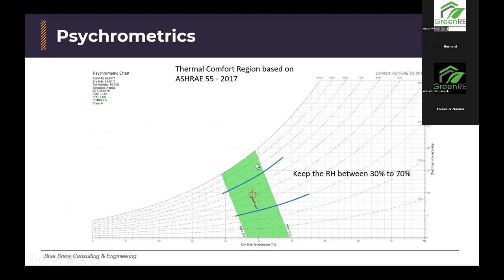As a human being, you may feel comfortable in an 80 RH region where the relative humidity is quite high, but it may not be conducive for the surfaces or the walls getting mold, or even equipment. So we normally try to keep the RH level between 30 to 70. We don't want to go any lower, because below 30 you run the risk of static. You get a lot of static on the surfaces. That is why even data centers don't drop below 30.